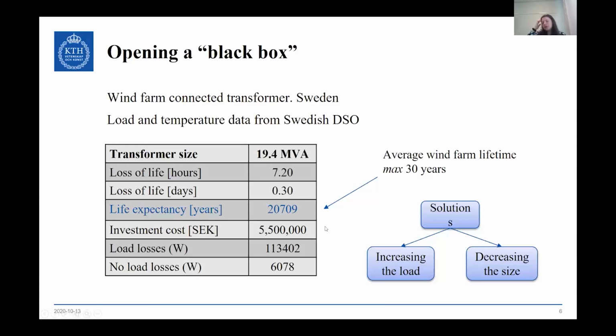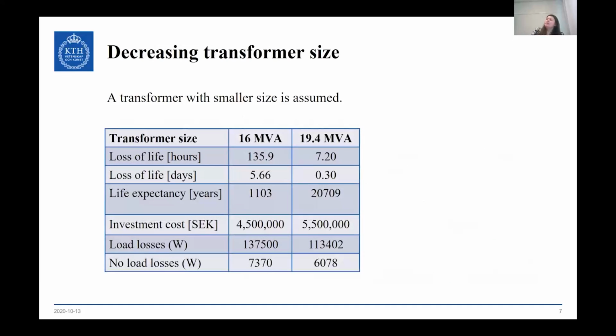So we looked into two ways to use this: first is to increase the load, and the second is to decrease the size. When we decreased the size of the transformer from 19.4 MVA to 16 MVA, you could save around 1 million kroner approximately, but your insulation lifetime expectancy is still very large. So you could potentially save a lot on investment. But if you plan future wind farms, you still have very high safety in your operation.